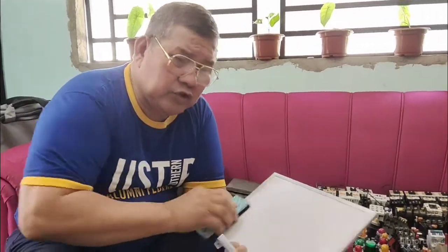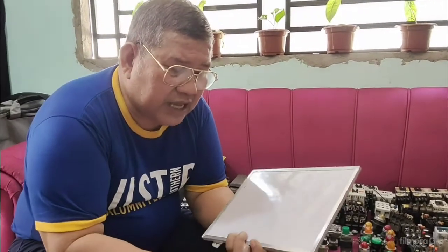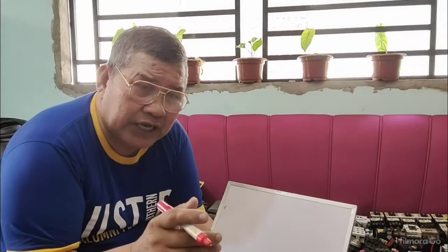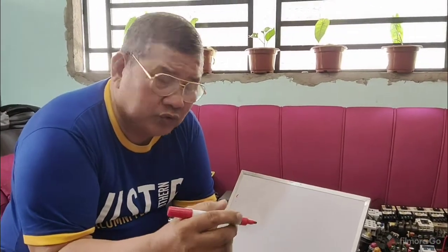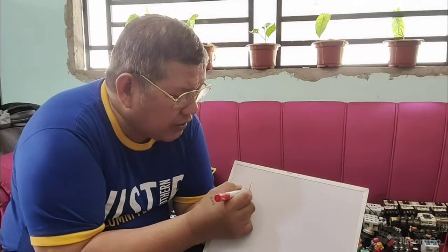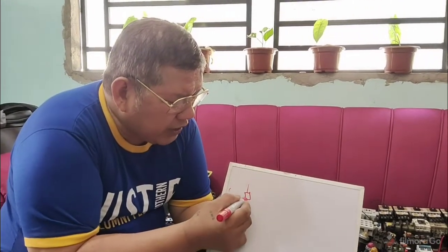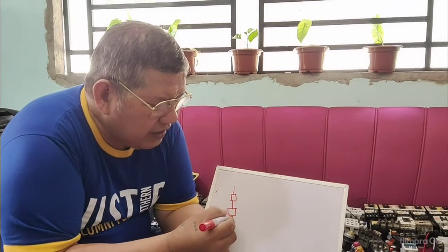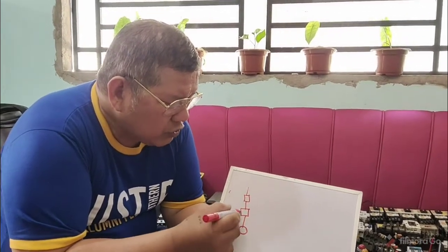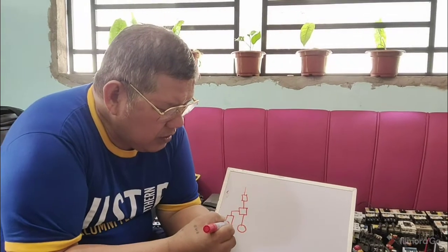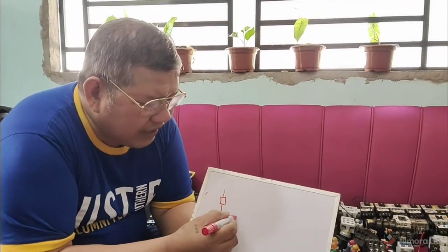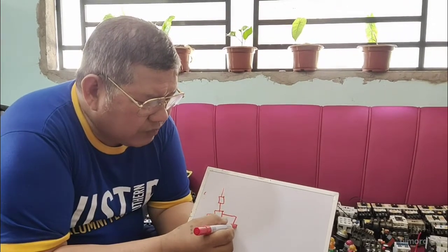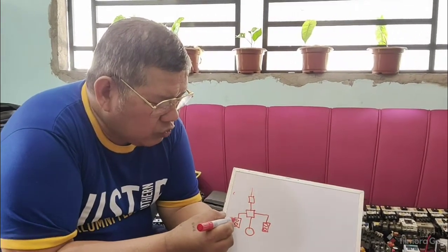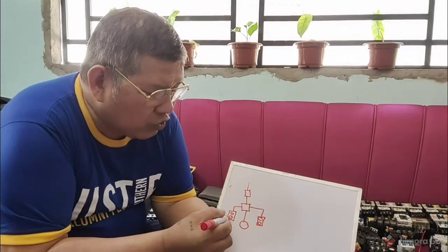We will use the same power circuit, but this time we will be using 2 push buttons, 2 stop buttons and 2 start buttons, meaning you have station 1 and station 2. For instance, this is your single line diagram: you have your circuit breaker, your magnetic starter, and your motor. So you have 1 push button here, and maybe on the other side another push button, meaning 2 start buttons and 2 stop buttons.